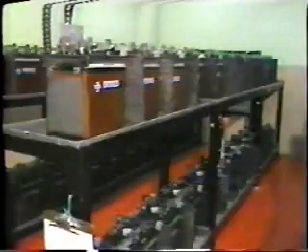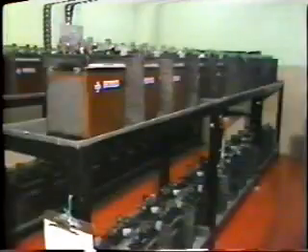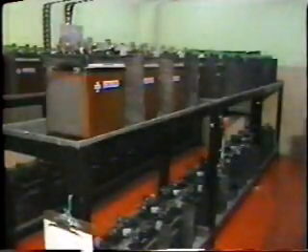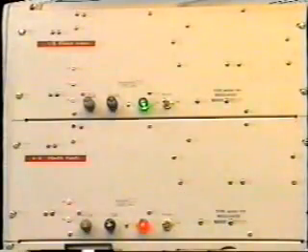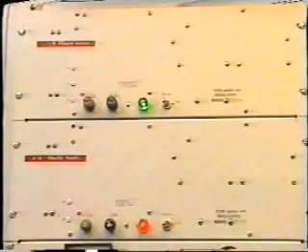First, the power supply. The carrier equipment is usually operated from the station battery, say 125 volts. Other arrangements exist where a 250 or 48-volt battery is used. There is also a PLC power supply available that will run off 120 volts AC. This requires the installation of an inverter so that the carrier can continue to operate from the battery during power outages. The power pack in the carrier provides the special voltages for the carrier electronics.